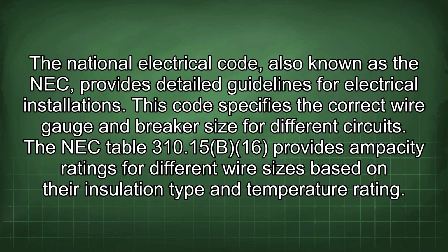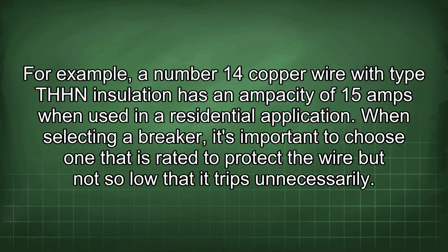The National Electrical Code, also known as the NEC, provides detailed guidelines for electrical installations. This code specifies the correct wire gauge and breaker size for different circuits. The NEC Table 310.15(B)(16) provides ampacity ratings for different wire sizes based on their insulation type and temperature rating. For example, a number 14 copper wire with type THHN insulation has an ampacity of 15 amps when used in a residential application. When selecting a breaker, it's important to choose one that is rated to protect the wire but not so low that it trips unnecessarily.